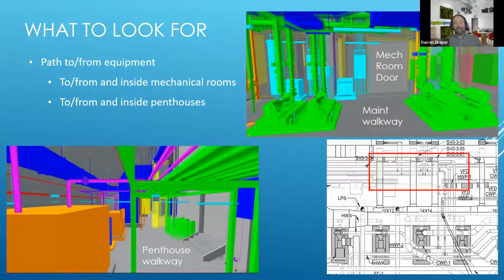The top right is a recent example for us that lines up with the snapshot from the plans where we had these 4 pumps in a row, and just to plan north, you see that red box identifying the area of this double door. In 2 dimensions it doesn't look terrible that you're walking into this mechanical room and run into these pumps - you think maybe you've got some space, but when we looked at this in 3 dimensions, we noticed you really don't have any room.